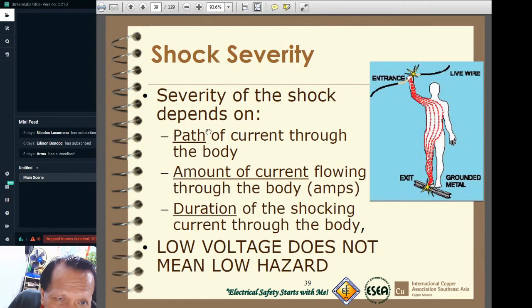Okay, so the severity of the shock depends on the path of current through the body and the amount of current flowing through the body, that's the amperes. The greater the amperes, the more lethal when the current is higher. And of course, the duration of the shocking current through the body. The longer a person is touching a live wire, meaning electricity is passing through his body, the more lethal it is, no? It doesn't mean that low voltage is of lower danger. No, what is really dangerous is the current that may flow through the body.